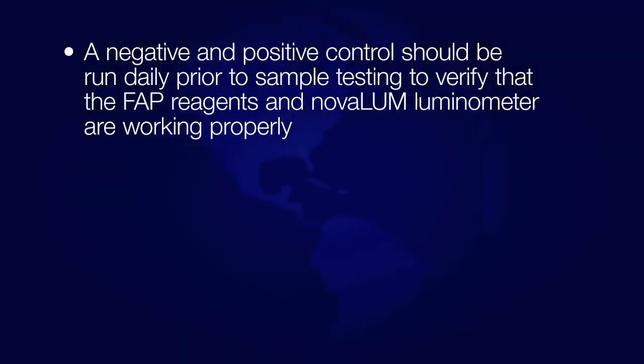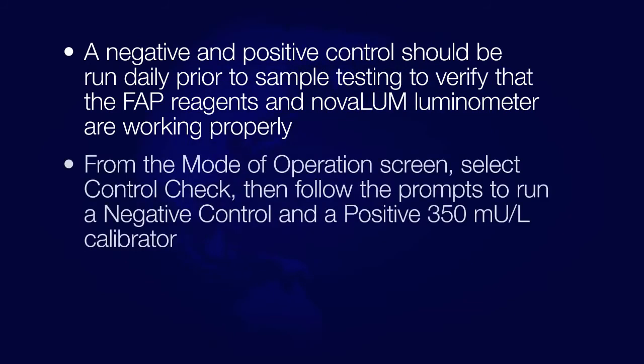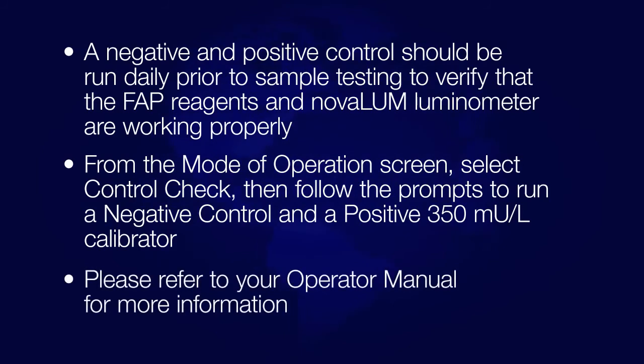A negative and positive calibration should be run daily prior to sample testing to verify that the FAP reagents and novaLUM luminometer are working properly. From the Mode of Operations screen, select Control Check, then follow the prompts to run a negative control and a positive 350 mU per liter calibrator. Please refer to your operator manual for more information.